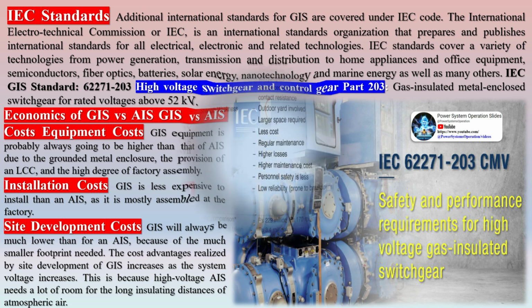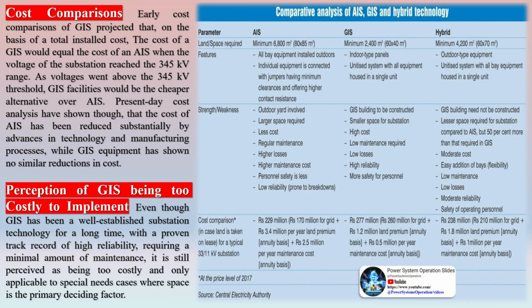IEC GIS Standard 62271-203: High-voltage switchgear and controlgear, Part 203, gas-insulated metal-enclosed switchgear for rated voltages above 52 kV. Early cost comparisons of GIS projected that, on the basis of total installed cost, the cost of a GIS would equal the cost of an AIS when the voltage of the substation reached the 345 kV range. As voltages went above the 345 kV threshold, GIS facilities would be the cheaper alternative over AIS. Present-day cost analyses have shown, though, that the cost of AIS has been reduced substantially by advances in technology and manufacturing processes, while GIS equipment has shown no similar reductions in cost.